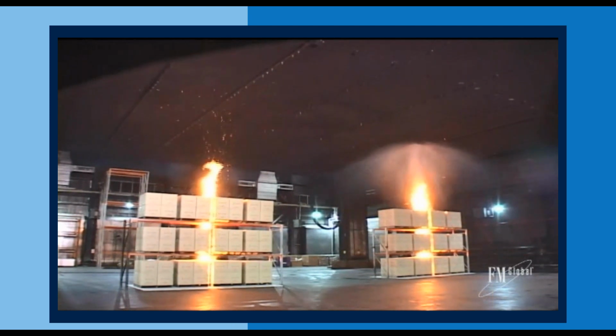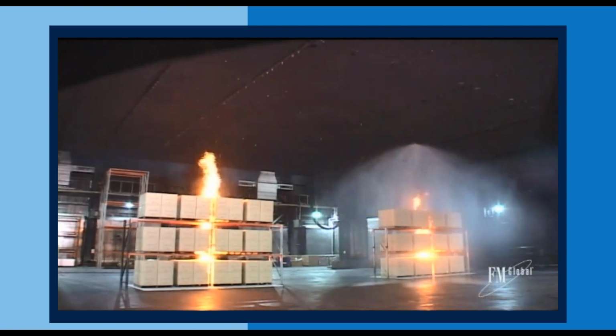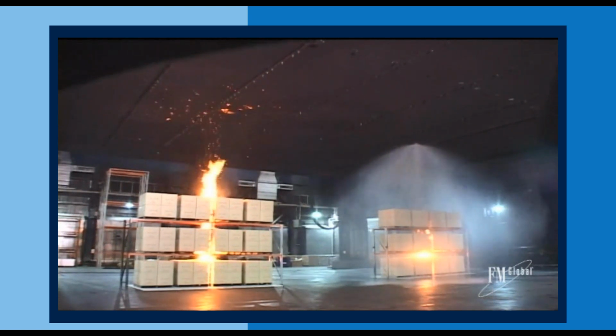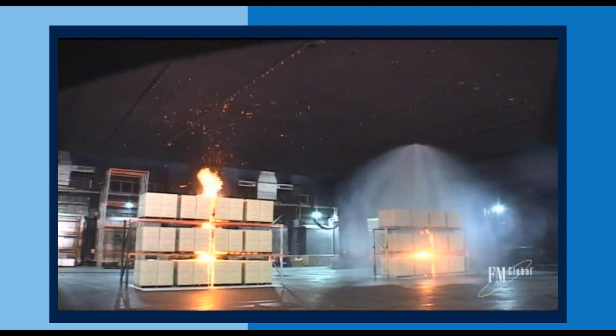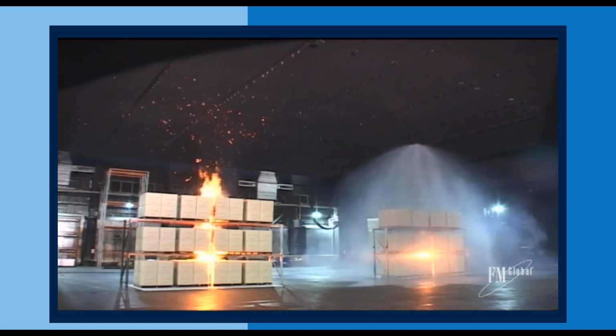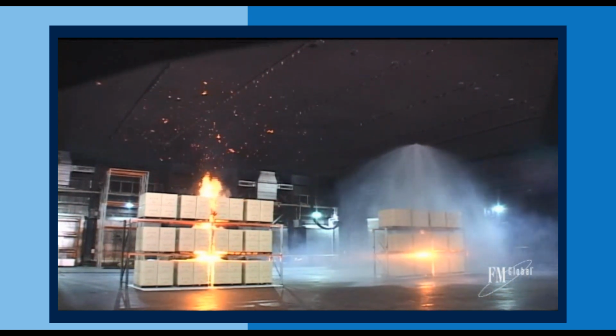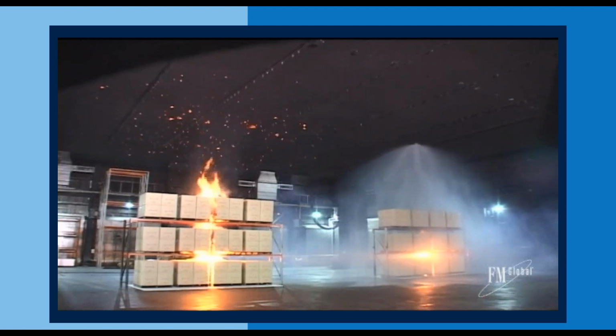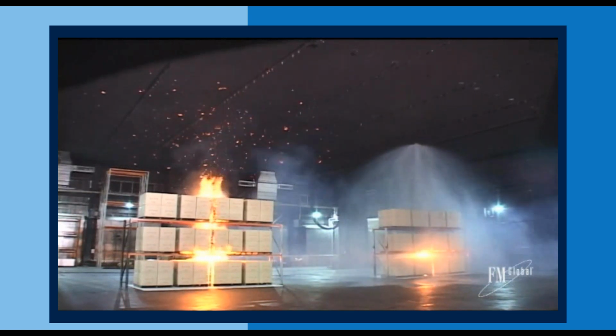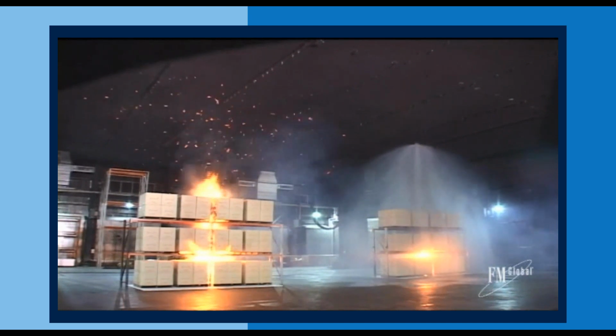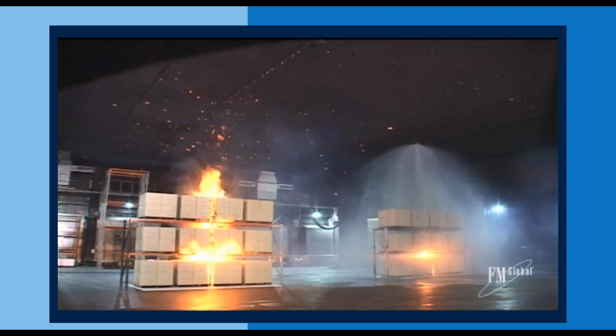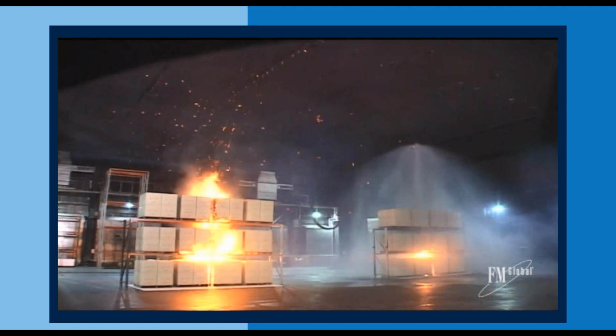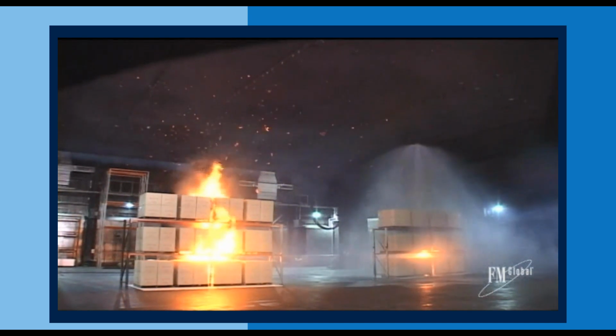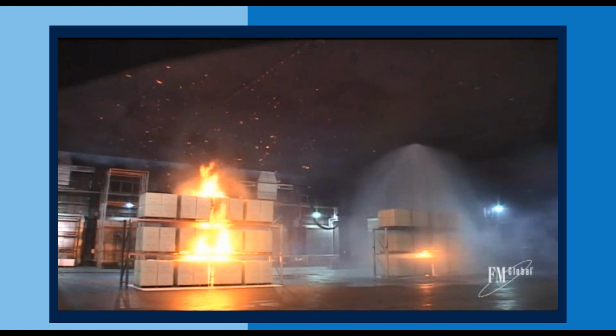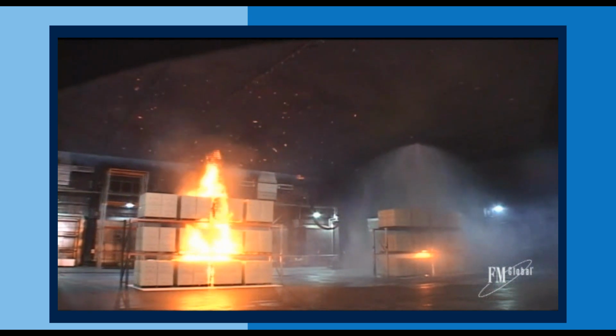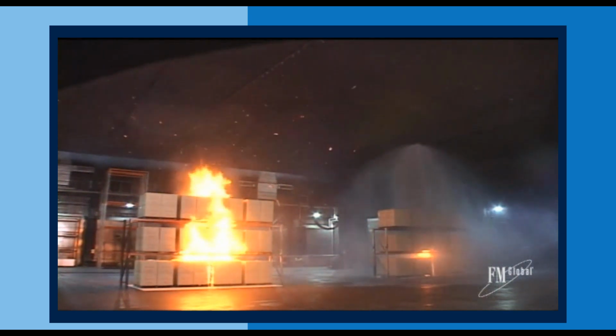Now, just over the minute, you're seeing a sprinkler head operate to control one of the arrays. The array on the left-hand side of your picture has no sprinklers. So you're seeing quite a lot of water being deployed from one sprinkler head over the array on the right. That's starting to knock down the fire and control it. You're seeing some steam and some light smoke coming off that one. The image on the left, the fire is just continuing. And that fire will continue until somebody either applies water to it or that array runs out of fuel.